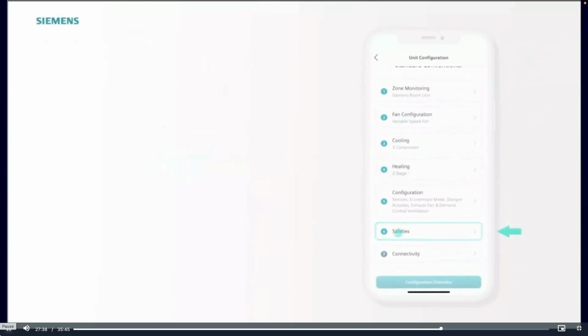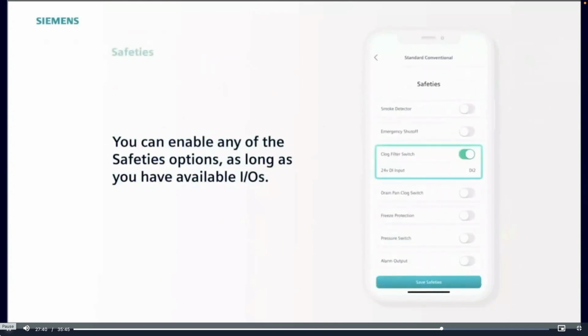The 6th step is safeties. You can see here the clog filter switch preset to DI2. This is preset to match the differential pressure switch in our RTU kit. You can enable any of the other options provided you have IOs available.